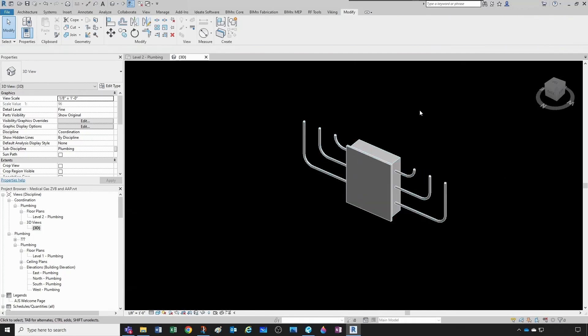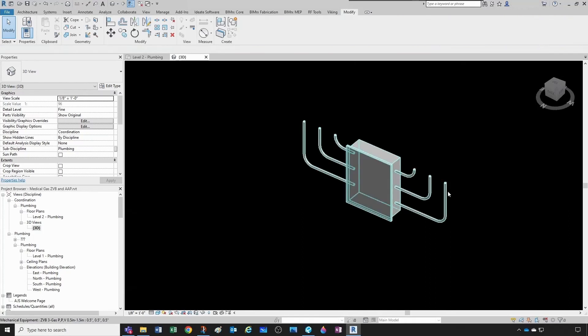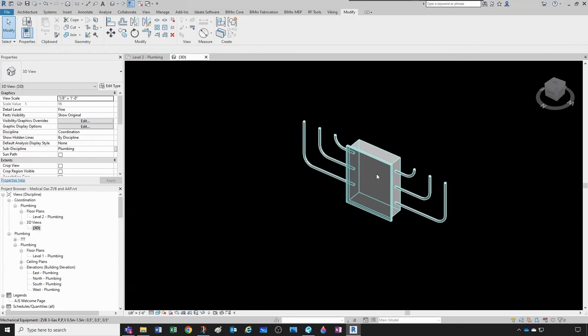For example, for medical air the outlets are on the right and the compressor is on the left. For oxygen, the outlets — medical booms, head walls — are on the right, and the oxygen farm or tanks are on the left. For vacuum, the medical outlets are on the right and the vacuum pump is on the left. The only thing that changes is the direction of flow: pressure pipes flow from source through the valve box to the outlets, while vacuum flow reverses — coming from the outlets through the valve box to the vacuum pump.